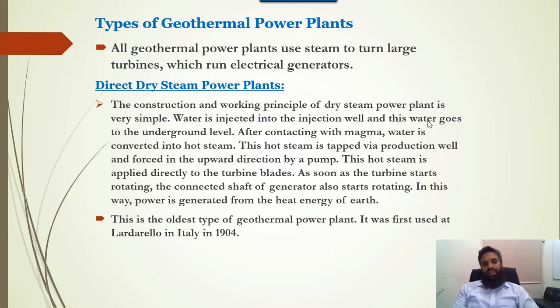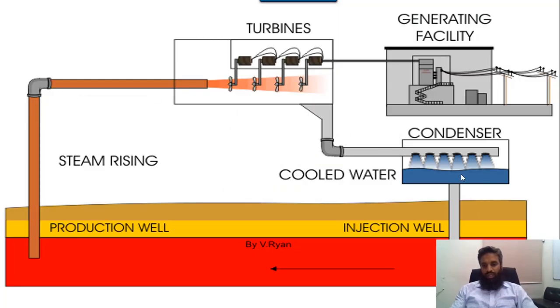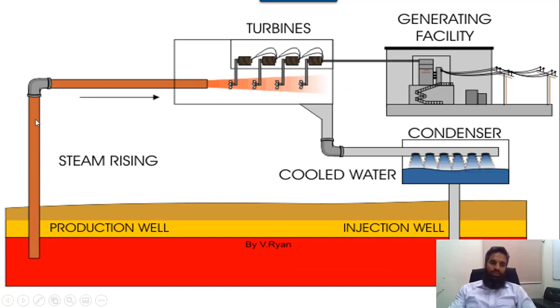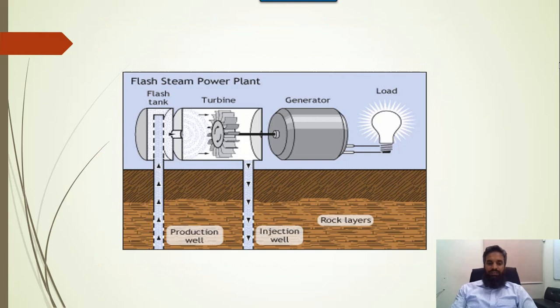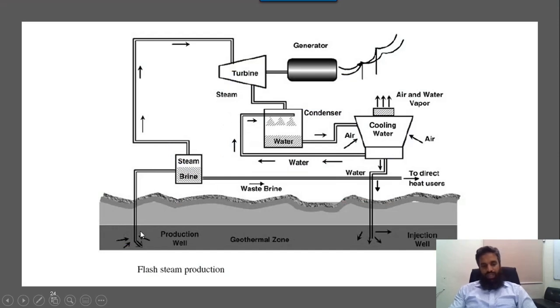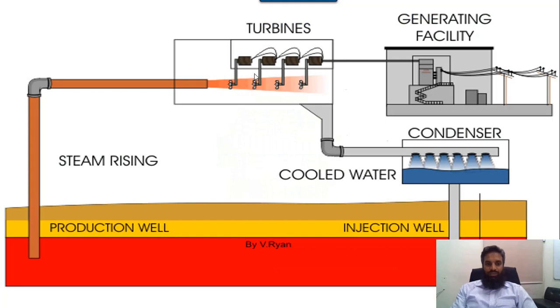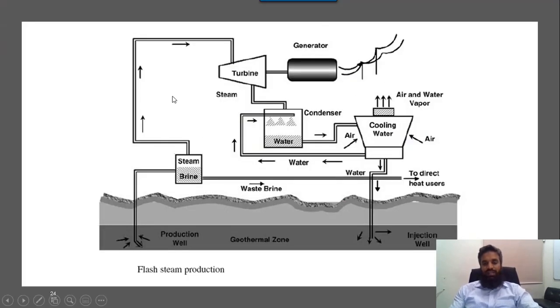There are multiple types of geothermal plants. The first is the direct steam power plant: water flows from the injection well to the geothermal region, steam travels from the geothermal region to the production side, and then the turbine rotates, driving the generator to produce electricity fed to the grid. The second type is the flash or double flash steam plant. In this design, there is an injection well and a production well; from the production well a flash tank stores the steam before it goes directly to the turbine, unlike the dry steam type where steam goes directly to the turbine.